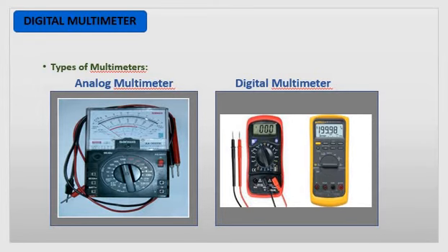To measure the resistance, current flows from a constant current source through the unknown resistance, and the voltage across the resistance is amplified and fed to the analog to digital converter, and the resultant output in the form of resistance is displayed on the digital display.